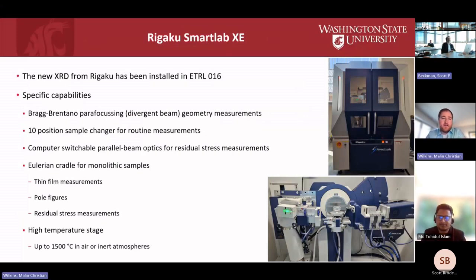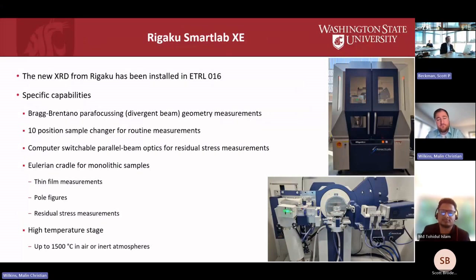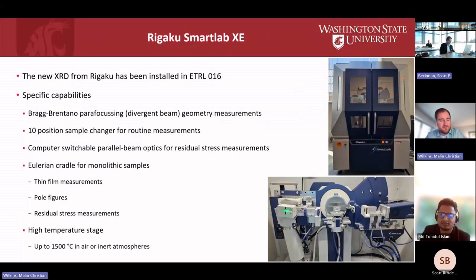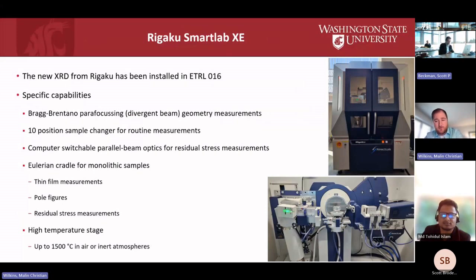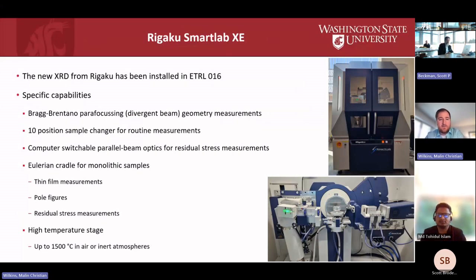In terms of the capabilities, we have basic Bragg-Brentano divergent beam measurements with a sample changer, which means we can set and forget — load 10 samples, come back the next morning, and have a nice diffraction pattern ready for analysis.